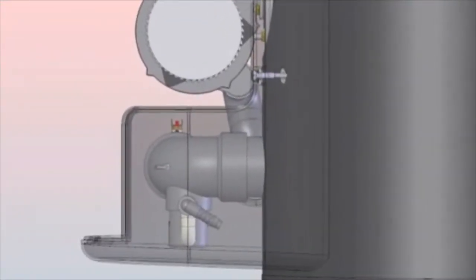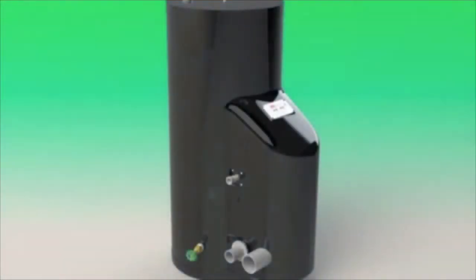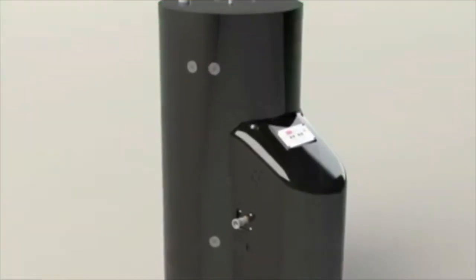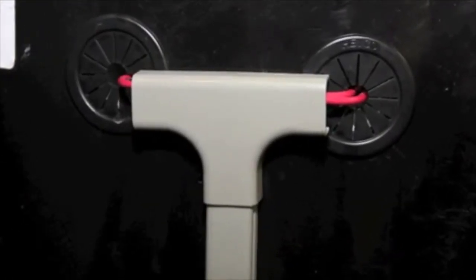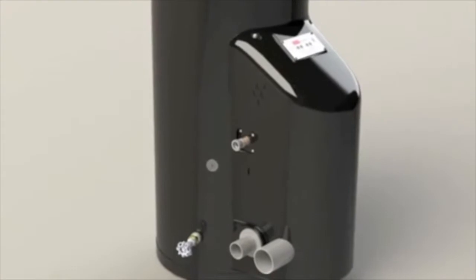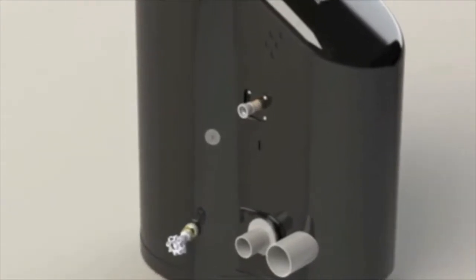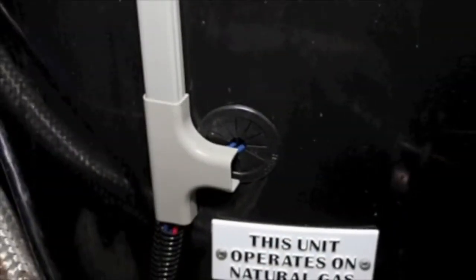The top water temperature sensor monitors supply temperature, and the control module adjusts heater firing rate to correct supply temperature. The bottom water temperature sensor monitors return water temperature, and the control module reduces or increases heater input accordingly.